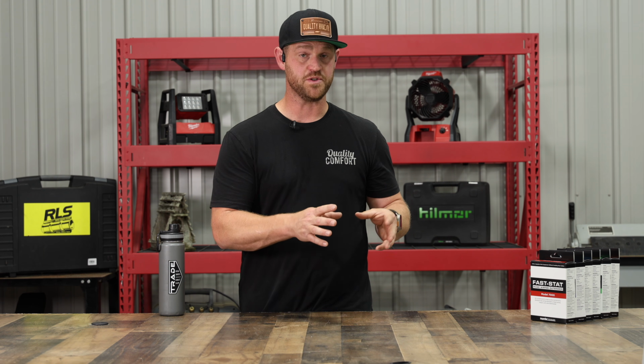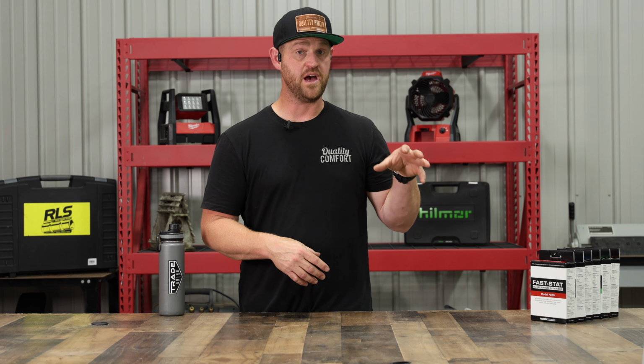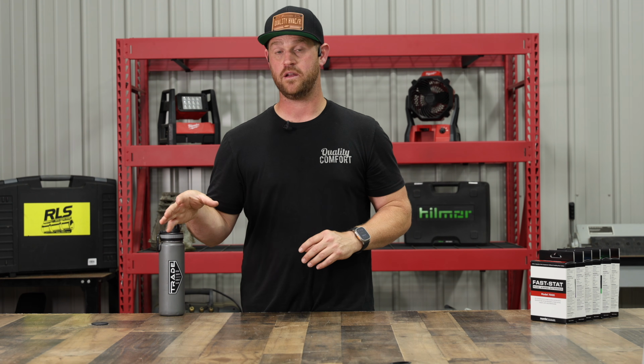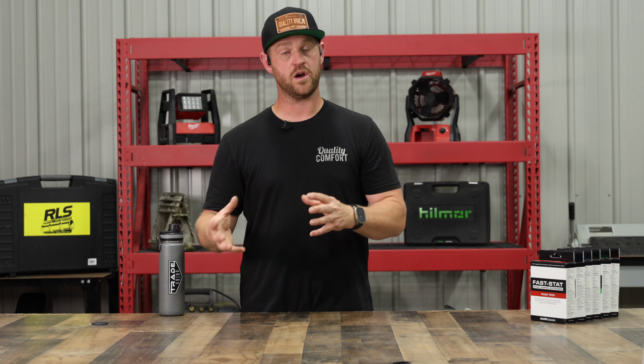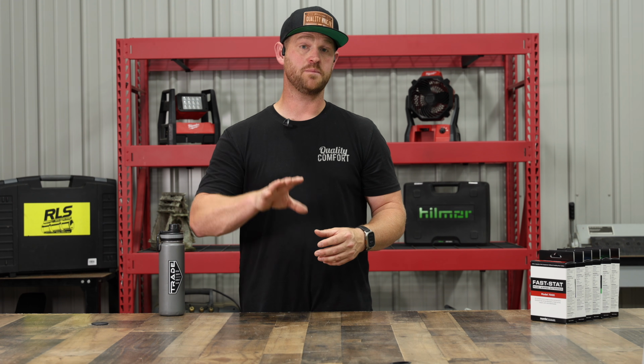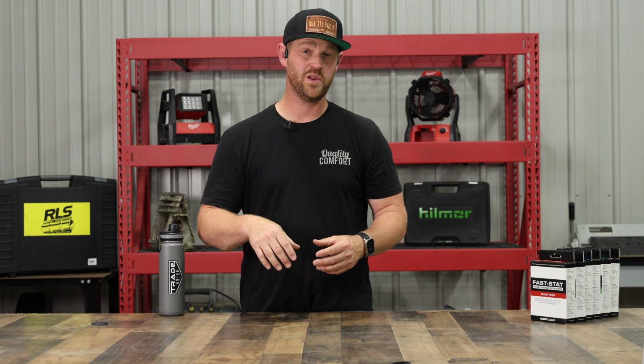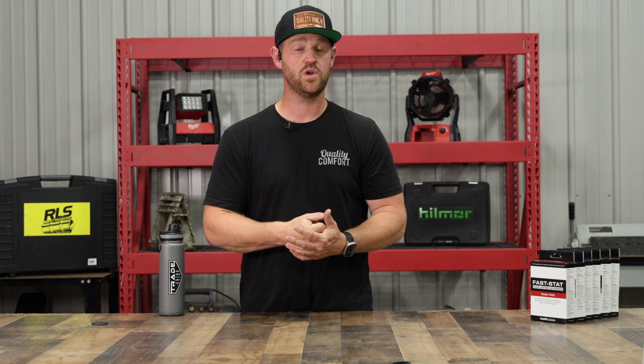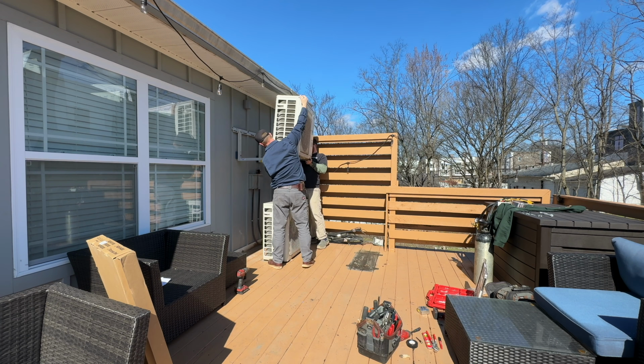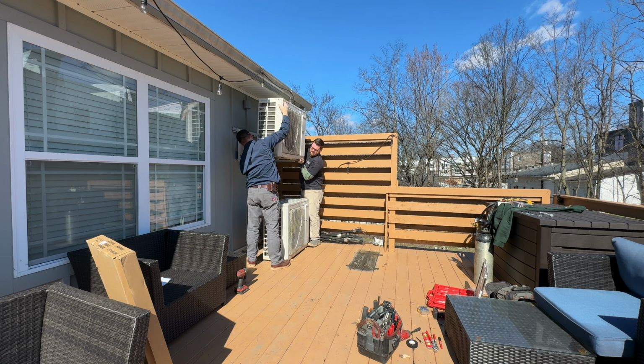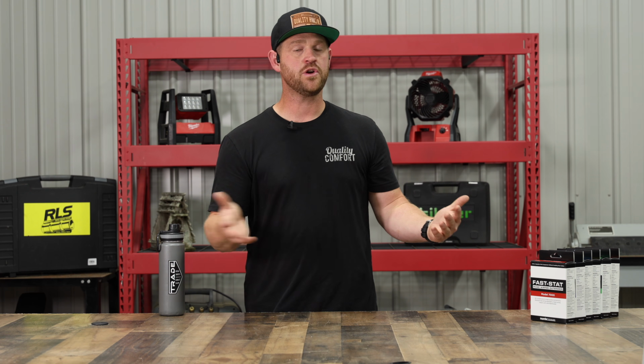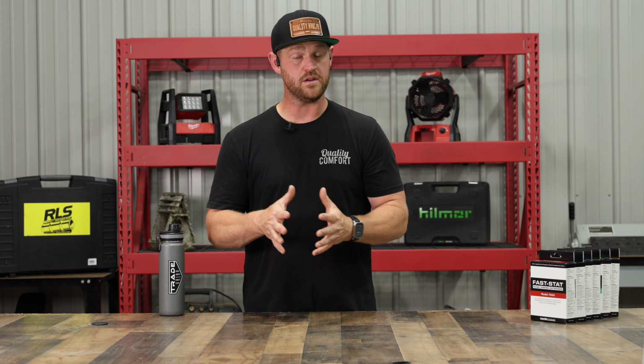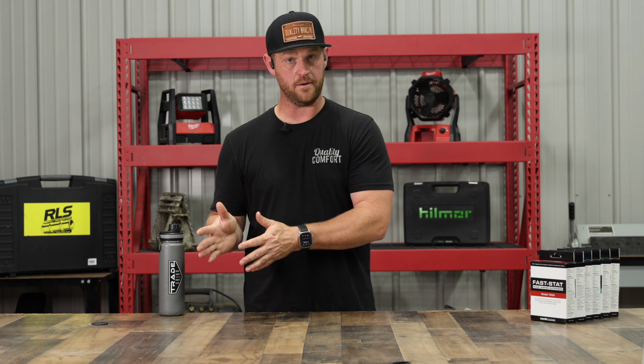Going back to variable speed, the outdoor compressor, the outdoor fan, and the indoor fan typically are all variable speed. So they're going to start up slowly. They're going to ramp down slowly. There's no kicking on and off really loud. So it's a very quiet system. You can have it right outside your bedroom window if that's the situation that you're in, and you're not even going to hear the equipment. So that is a really good option and reason why to go that route as well.